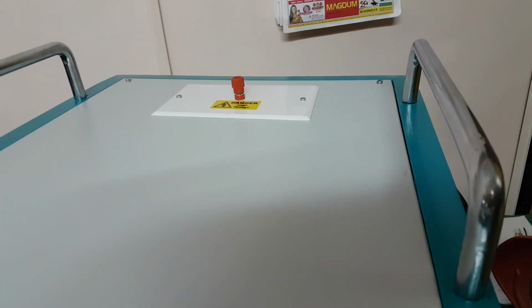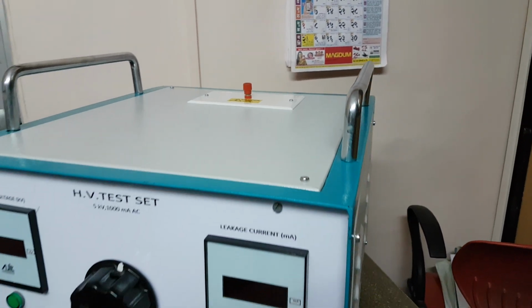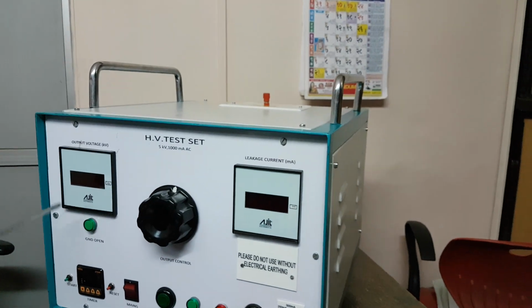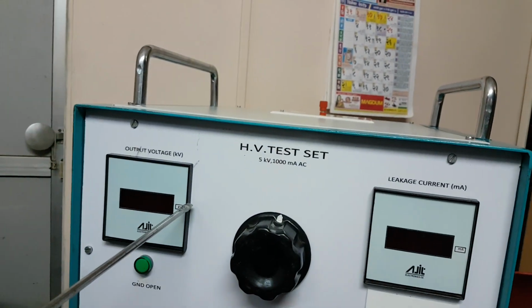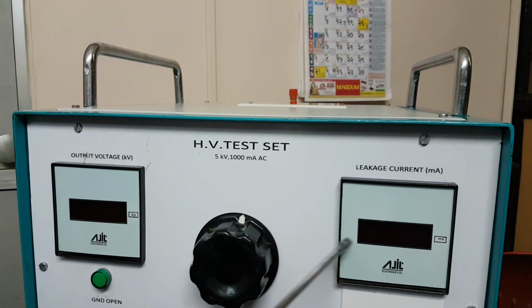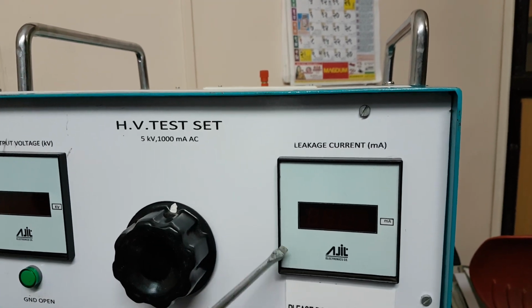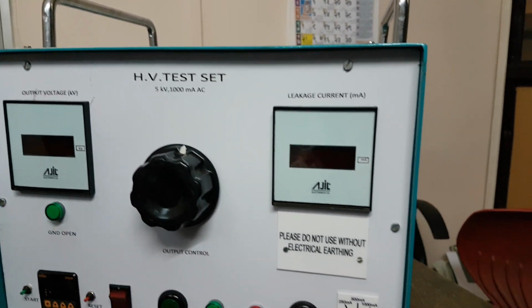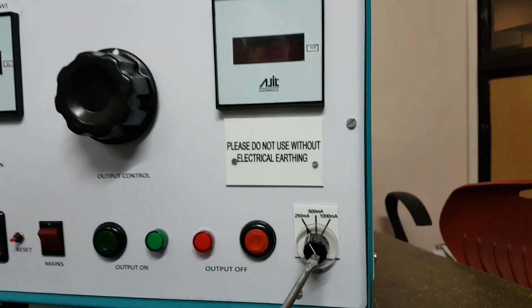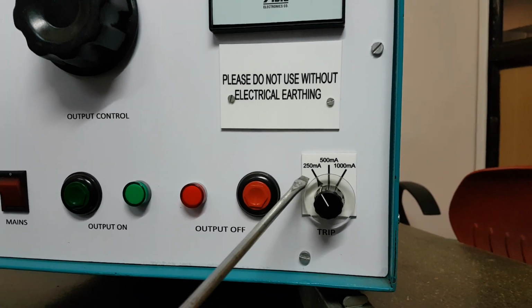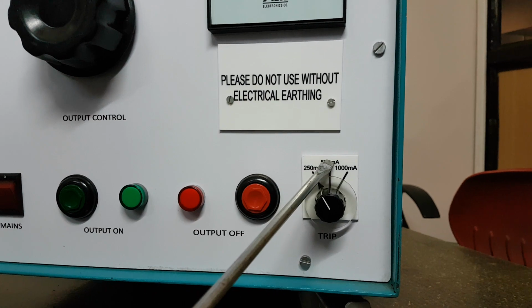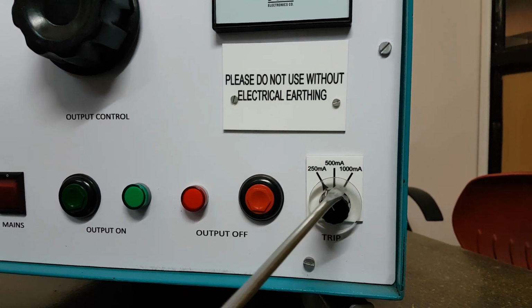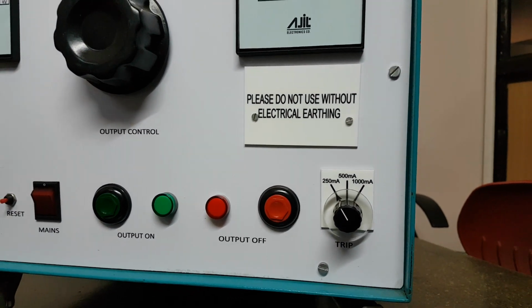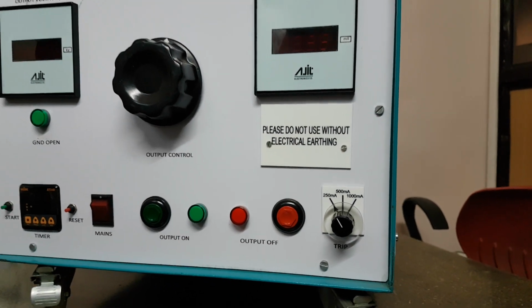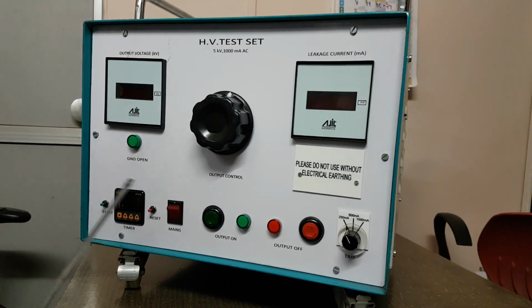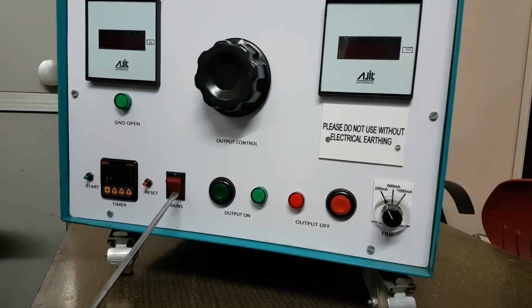Okay, and here you can see this is the output voltage meter. This is the leakage current meter. Then this is the leakage current limit selector: 250 milliampere, 500 milliampere and 1000 milliampere. Here we can select the trip current, we can say, which is the limiting factor. From here, this is mains on off.